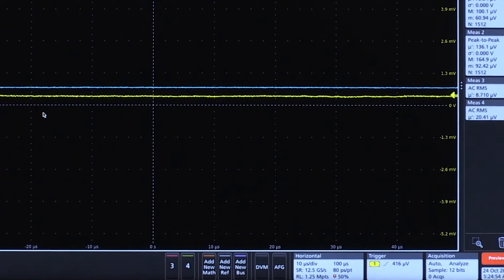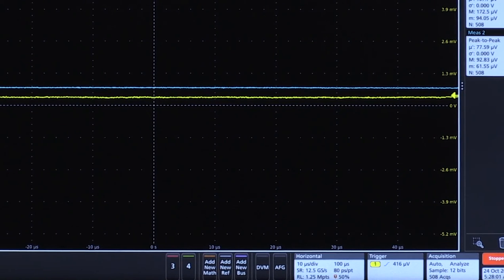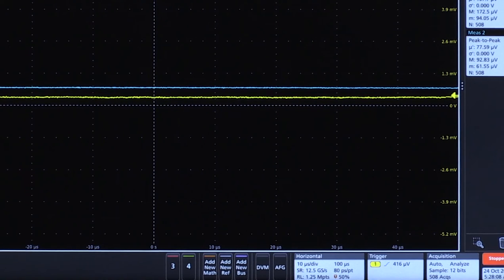First, I want to compare the baseline noise of the probe and the scope. As mentioned earlier, I want to take a look at the noise specs of the probe. Channel 1 is the probe plus the scope with the input shorted. Channel 2 is the scope with an open input. I've set both channels to 1.3 millivolts per div and set a 20 megahertz bandwidth limit, typical for power measurements.